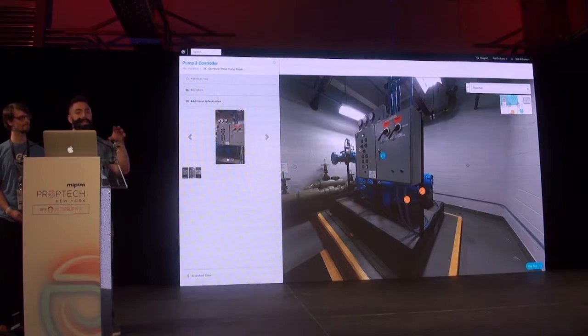So what we do by having our low-cost sensors and monitoring hundreds or thousands of pumps is creating this data library where we can take learned instances of where there was short cycling, what it looks like in the data, where there is schedule drift or set point drift, what it looks like in the data, hard coding that into an algorithm, and then reapplying that to the entirety of our client portfolio, so every building can benefit from one error in one system in one building.